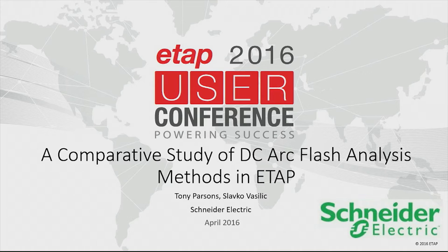And I think many of you are probably aware that at least since 2012, there has been an equation in NFPA 70E that we could use to estimate arc flash levels in DC systems. I don't know how many of you may be aware that there are also a couple of other calculation models out there that are also part of the ETAP software. So it just kind of got us to thinking, why do we need three different models? Which one is right? When should we use this one versus the other one? Started looking into it, some interesting things came out of it.